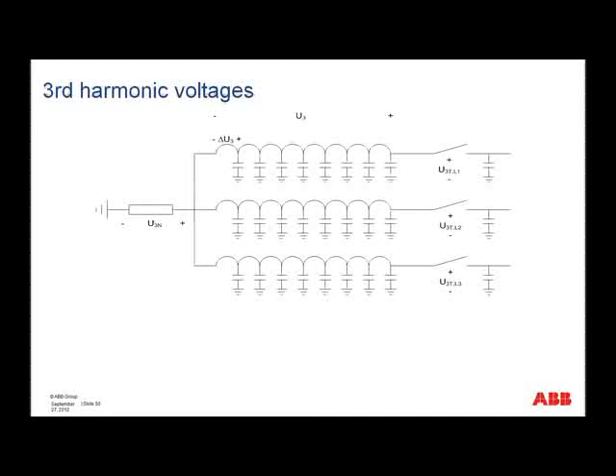So, as I said in the last slide, the third harmonic voltage is generated by the generator itself. It has the characteristic of a zero sequence component because it has the same phase angle in all three phases. The distribution of the third harmonic voltage depends on a number of things. It depends on the neutral point grounding method. It depends on the stator winding capacitance to ground. It depends here on the generator CB capacitance to ground. Not shown in the picture, but it depends also on the generator transformer low voltage delta winding capacitance to ground.